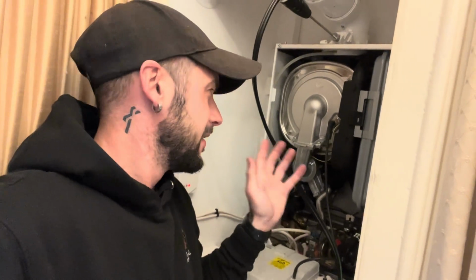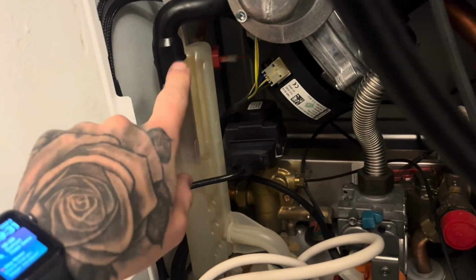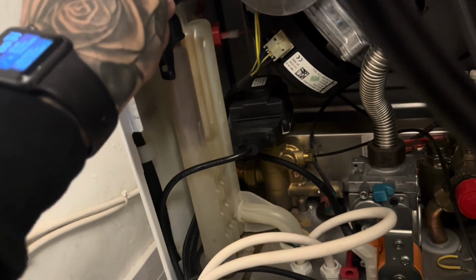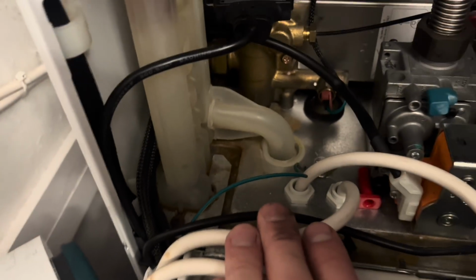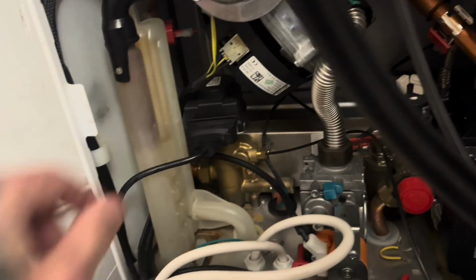These boxes are one of the easiest boilers in the world to service. Easy to strip down, just a dream. Well, the next one is this one's predecessor. Is that the right word? Just be mindful when you clean the condensate trap out, because this has an integral pipe as well, which sits inside the trap, and sometimes it won't go in properly, which is what I found out last time I serviced it, hence the rust mark down there. It hadn't gone in properly and wasn't sealed.